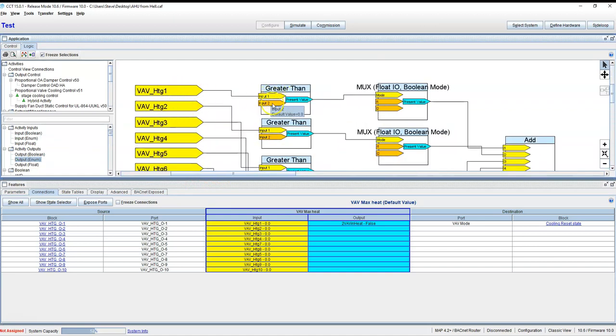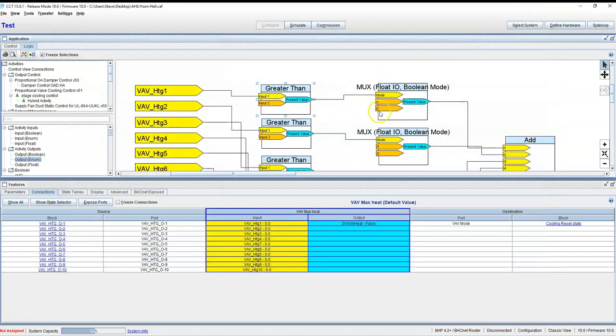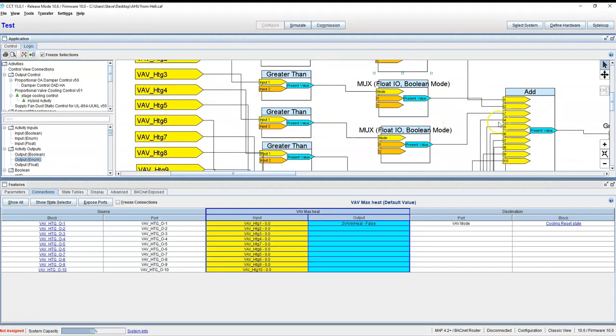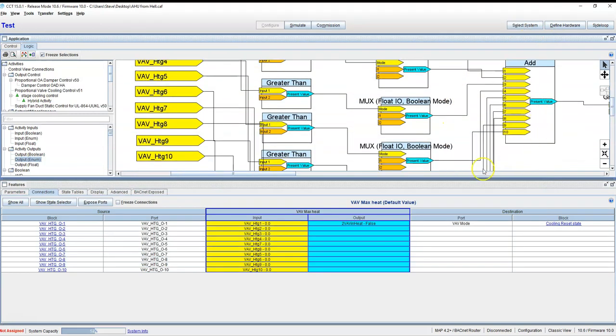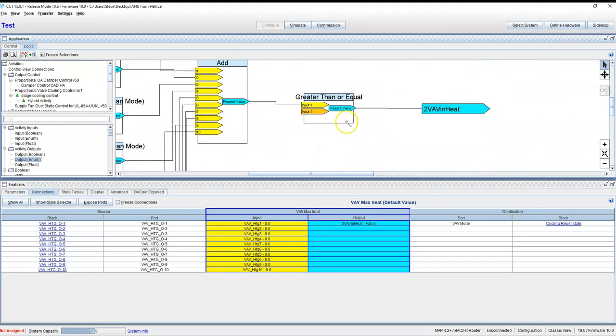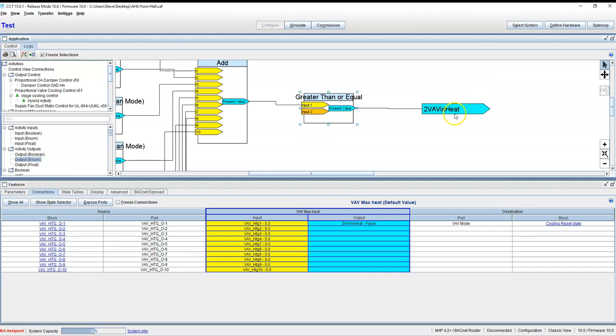Heating greater than zero—so if it's greater than zero it's going in this mux block. When it's true it's putting out a one, when it's false it's putting out zero. We're adding all the ones up and we're doing a greater than or equal to two, and we're sending the output out as a boolean state right here.